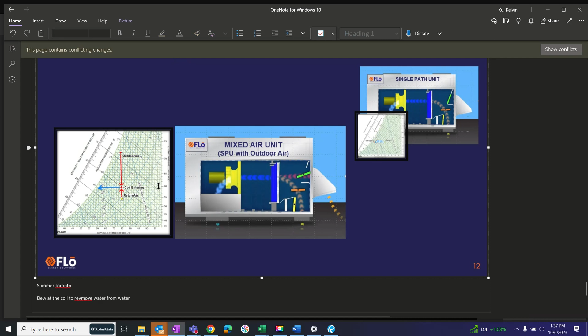No, I'm just kind of wondering about the whole refrigeration process, the coils and stuff like that, just getting some numbers for me. Yeah, so when we're in dehumidification mode, depending on the level of humidity that we are dealing with, we will drive the coil all the way down, even to 35 degrees. So the refrigerant and the coil, the suction temperature, if you want to call it that, is down to 35. So the coil is very cold.